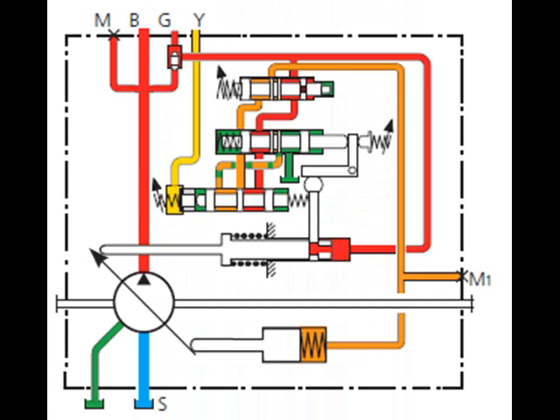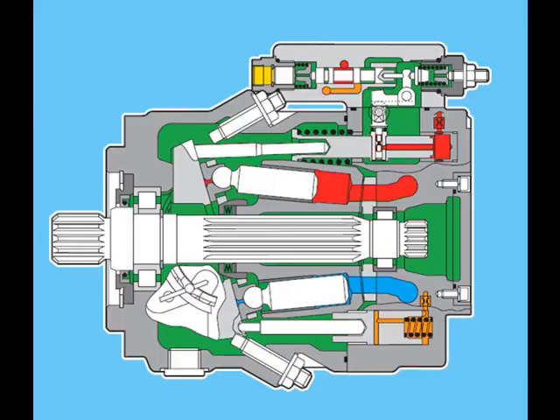LR Power Control with Stroke Limiter. The stroke limiter can be used to vary or limit the displacement of the pump continuously over the whole control range. The displacement is set in LRH with the pilot pressure PST, maximum 40 bar, applied to port Y, or in LRU by the control current applied to the proportional solenoid. A DC current of 12 V (U1) or 24 V (U2) is required to control the proportional solenoid.